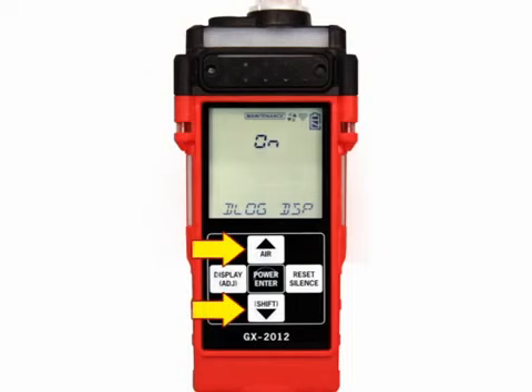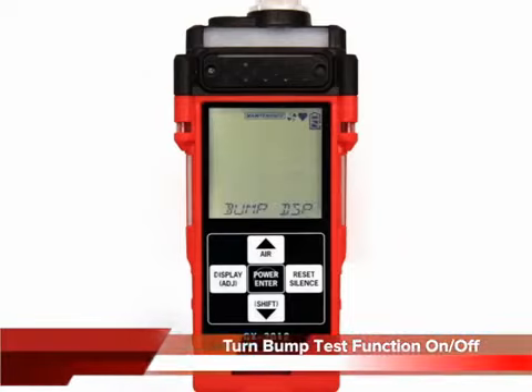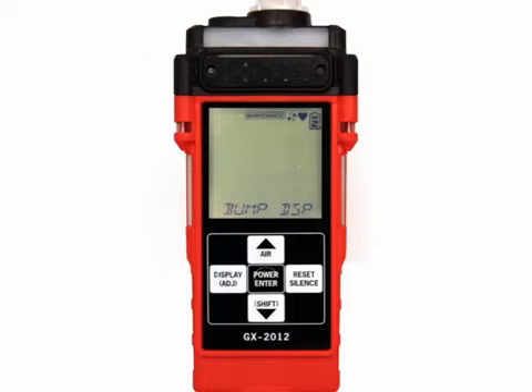Use the Air or Shift button to display the desired setting. Press and release the Power Enter button to save the setting and return to the main menu. The Bump Display menu item is used to turn the bump test function on or off. If set to off, the bump menu item in calibration mode and maintenance mode does not appear. In addition, the bump set, bump interval, bump reminder, and bump expired menu items will not display in maintenance mode. The factory setting is off.